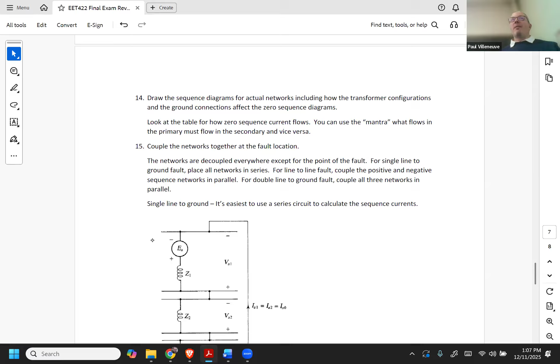If you get stuck, remember the whole point: what flows in the primary has to flow in the secondary. So if zero sequence current can't flow in the secondary, it sure can't flow in the primary. That's the whole purpose of a transformer, it steps current up or down. If current isn't allowed to flow on one side, it can't flow on the other, even if you think it can, because it reflects an infinite impedance to the transformer.